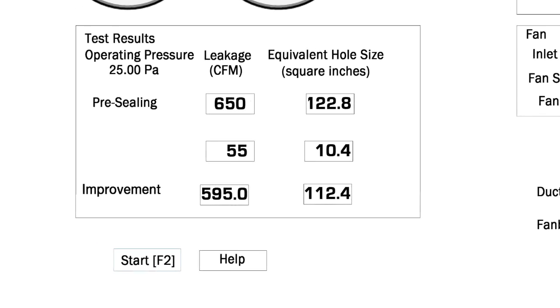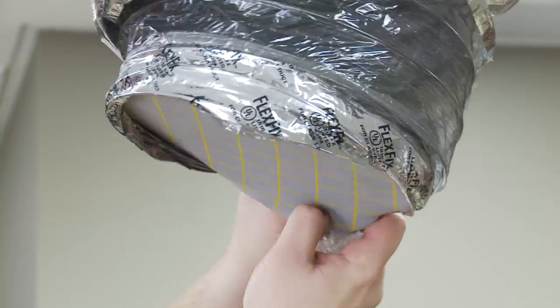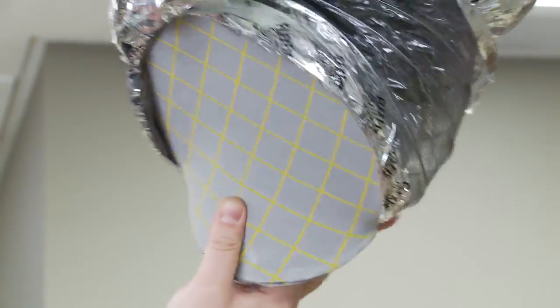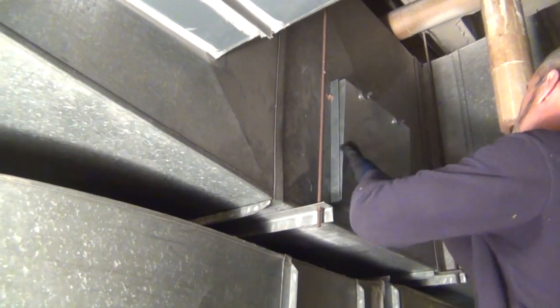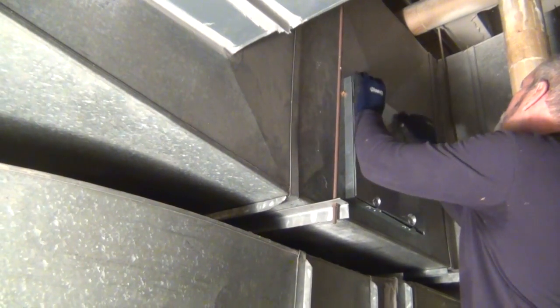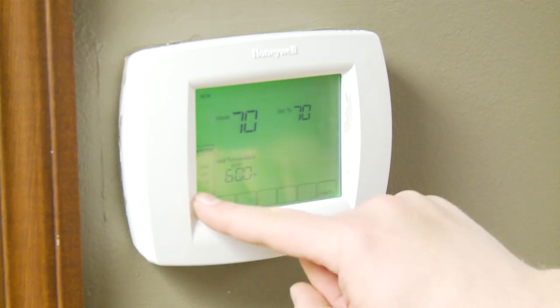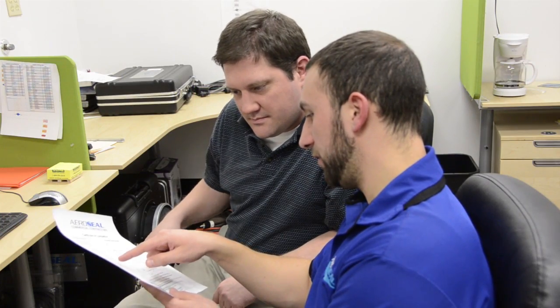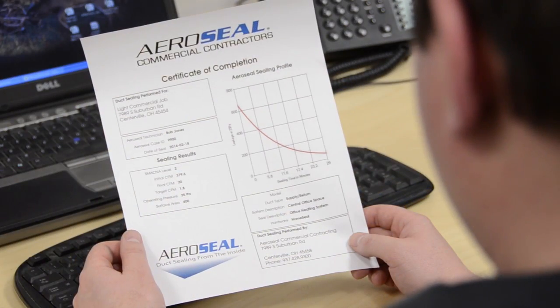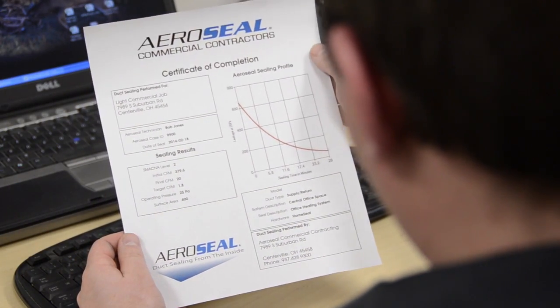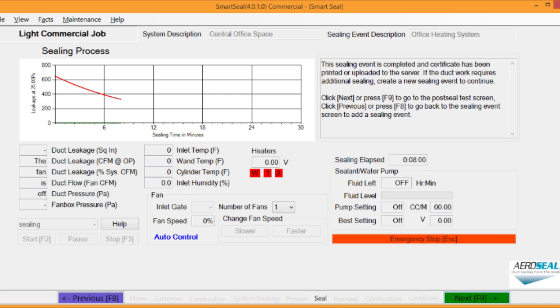After the post-seal test is complete, the technician removes the blocks from the diffuser and registers. All injection points are patched and the equipment is packed up. After all of that is complete, the HVAC is turned back on. A certificate of sealing results will be given to all Aeroseal customers. The certificate of completion states the initial leakage rate and the leakage rate after the seal job is complete, along with the graph representing the sealing process.